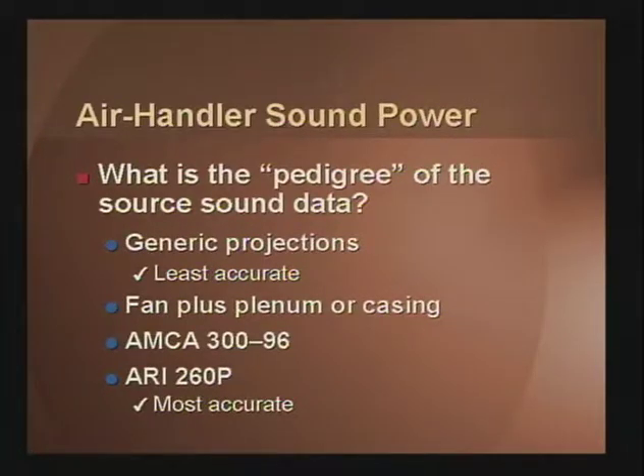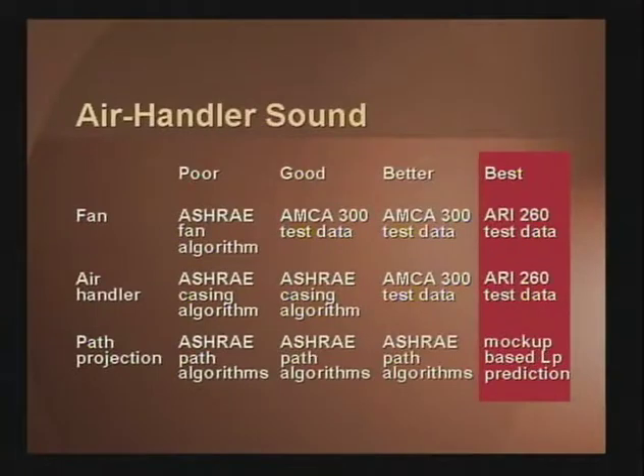A step beyond that, which is commonly used, is to do testing of the fan only using AMCA 300-96. The most accurate method available in the industry today is ARI 260P, which is sound power testing of the ducted air handler unit. Now that we've seen that there are different levels of quality of sound power information, the next slide explains how this information is being applied today to obtain air handler sound power level ratings.